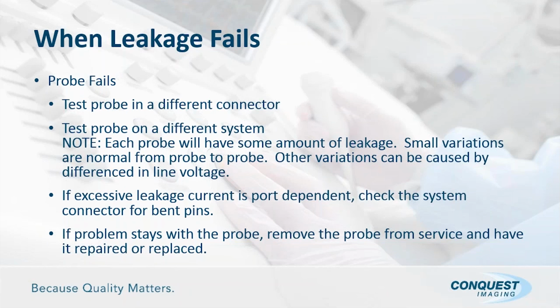This is an important concept. Even if the probe meets or exceeds NFPA 99 standards, after you've done as many electrical safety tests on probes as we do, it's clear that there's a limit, and even if it's meeting electrical safety, there can still be something wrong with the probe. An example is if you see a probe that leaks at 10 microamps, that's high. At that point, there's no doubt in my mind that there's something wrong with the probe, even though it may meet the standards that the OEM or NFPA gives you. It's clearly not right compared to all the other probes that we've been testing.